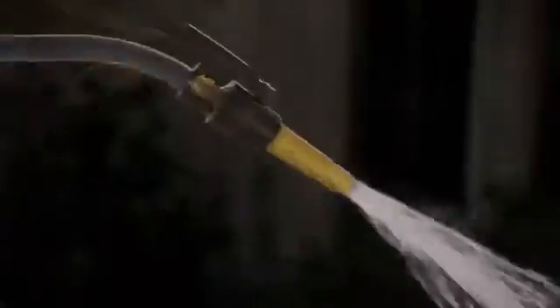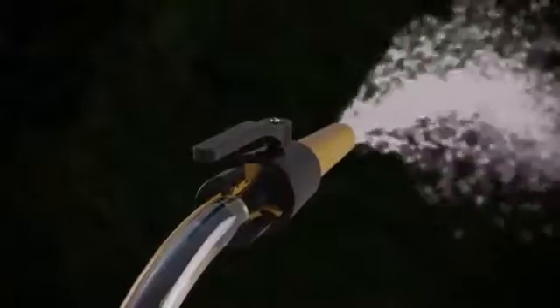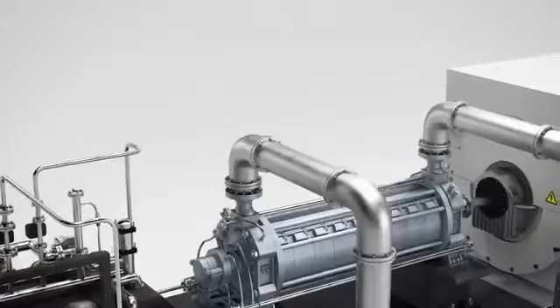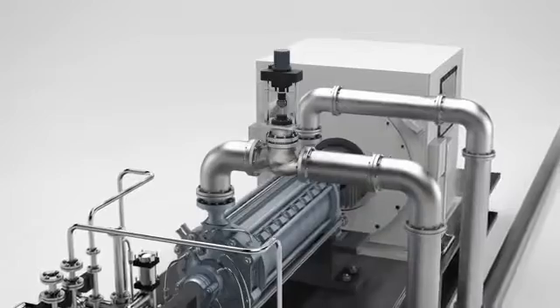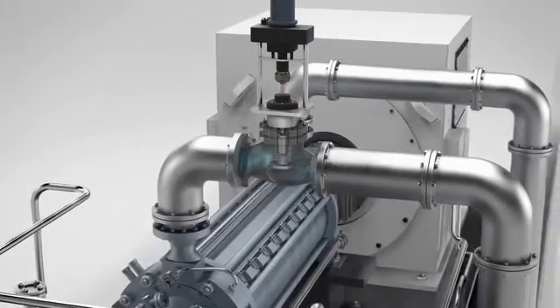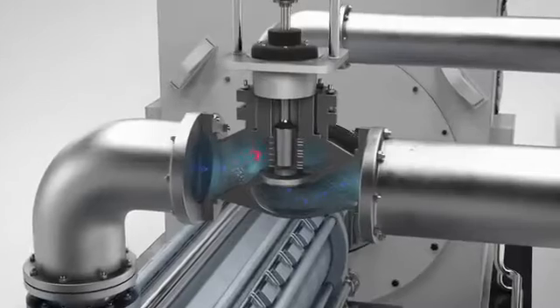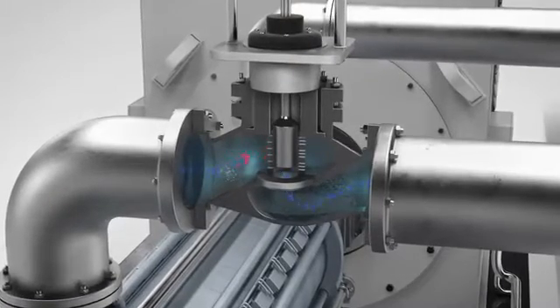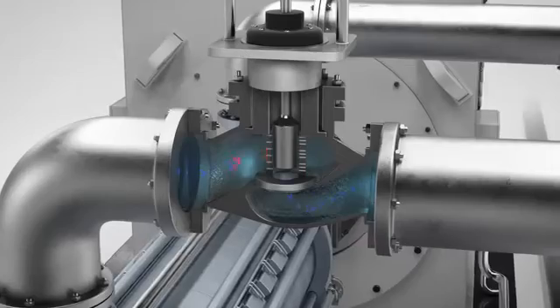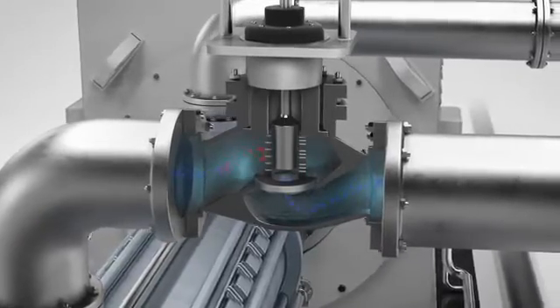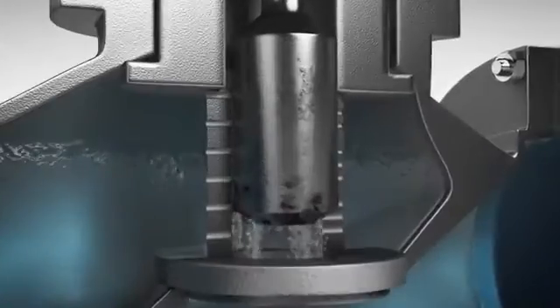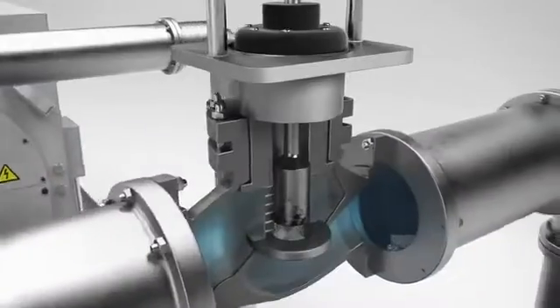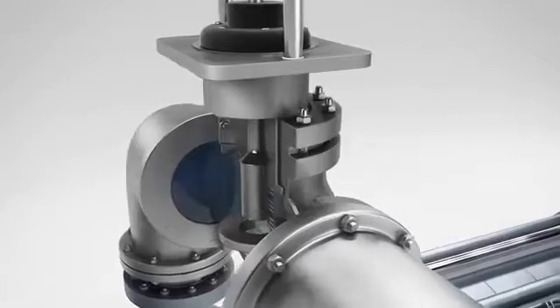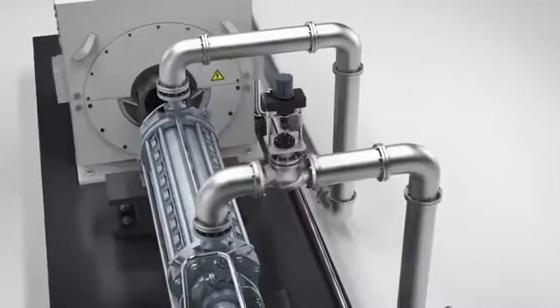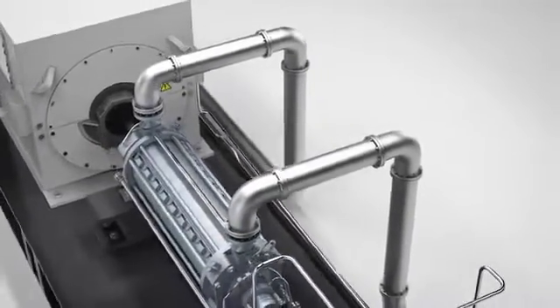Discharge throttling is similar to a garden hose, with the flows reduced by gradually closing the nozzle. This increases the water pressure in the hose. While the pump speed remains constant, a throttle valve in the feed water circuit generates resistance in order to reduce the flow volume. The result is increased pressure in the water supply line. In addition, it drastically reduces the hydraulic efficiency of the boiler feed pump. At the same time, the throttle valve experiences wear through cavitation, resulting in the expensive proposition of replacing valves along with a high level of vibration-induced noise. Energy waste, high maintenance costs, and inadequate reliability make discharge throttling a poor choice for modern power plants.